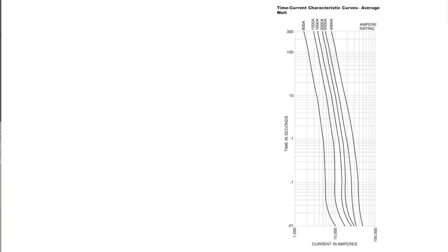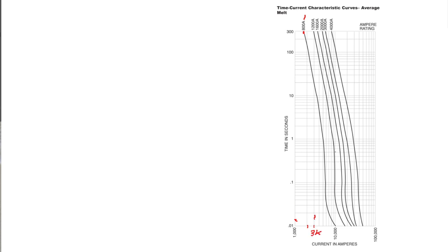Let's look at an example. Let's say we have an 800 amp fuse, so we look at this line right here, and let's say we have a fault current of around 3,000 amps. So if this is 1,000, then 2,000, 3,000—this is our fault current. All we do is follow the fault current all the way up to where it intersects this 800 amp line, which it does right around here.